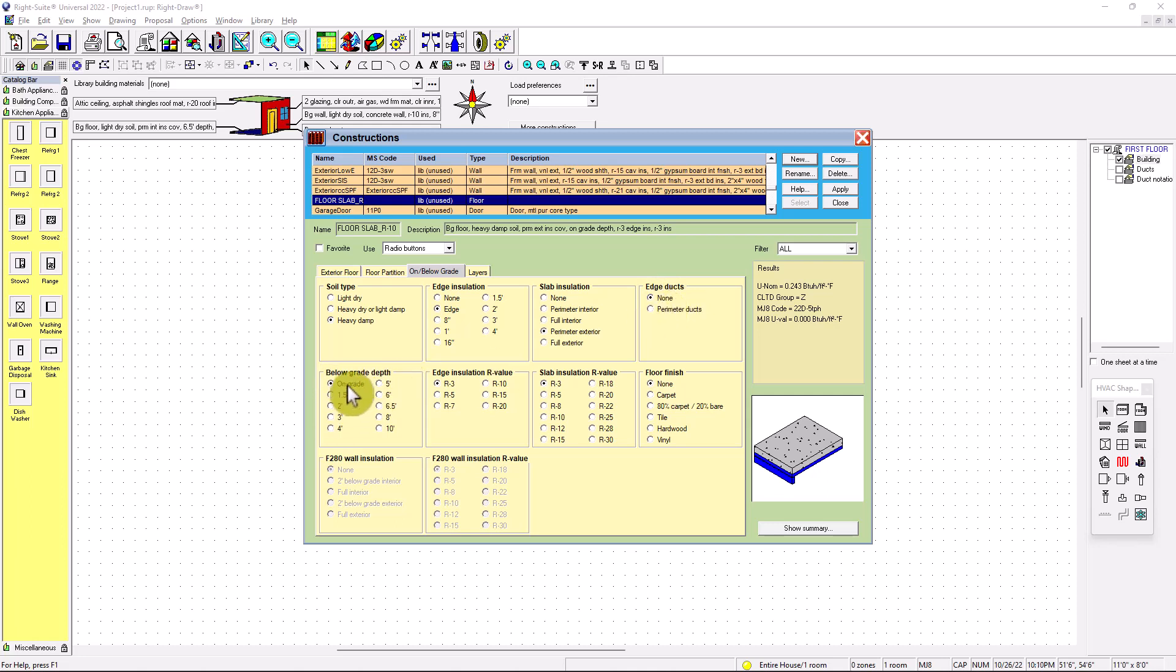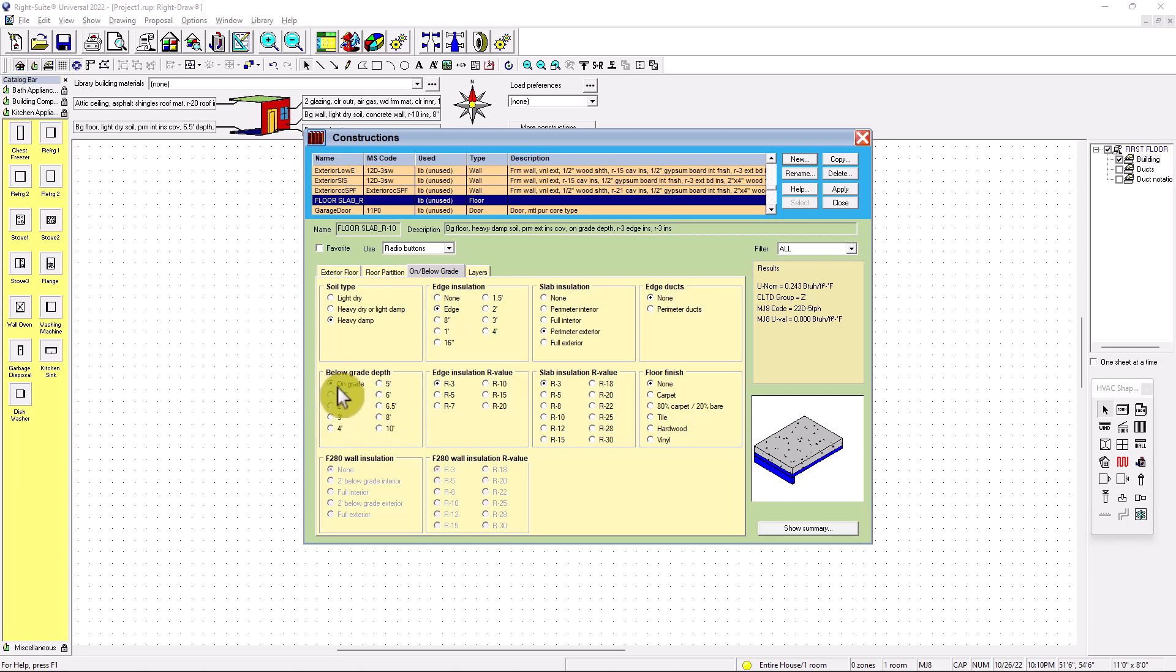And then below grade, no, it's on grade. But if you're doing for a basement, then you're going to have to put the below grade depth, 6 feet or 4, or however you consider this. If it's a crawl space, it's different. So for now, since it's on grade, we put on grade. Now for edge insulation, we're going to put R10. That's why I called it R10.